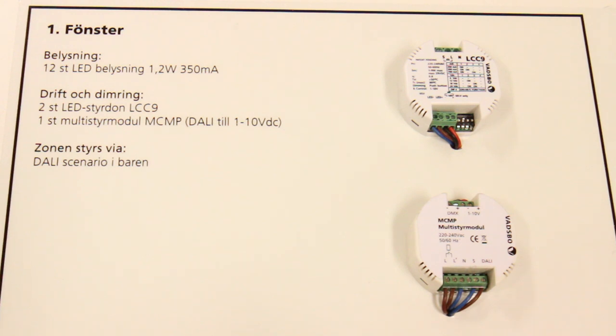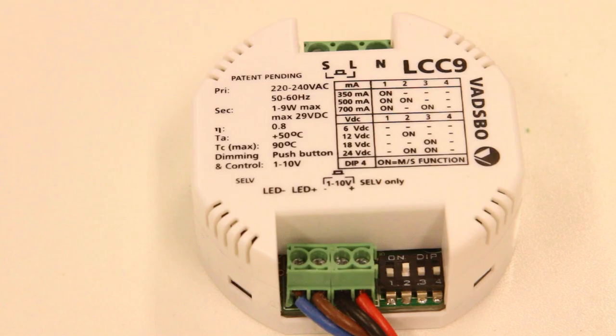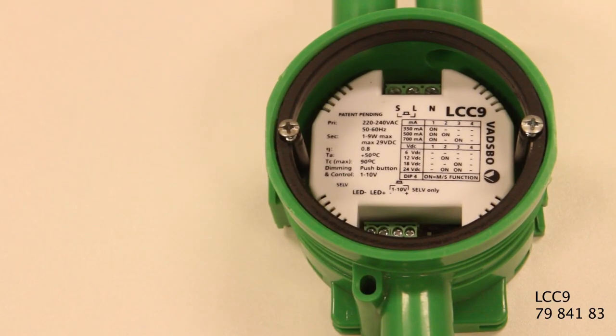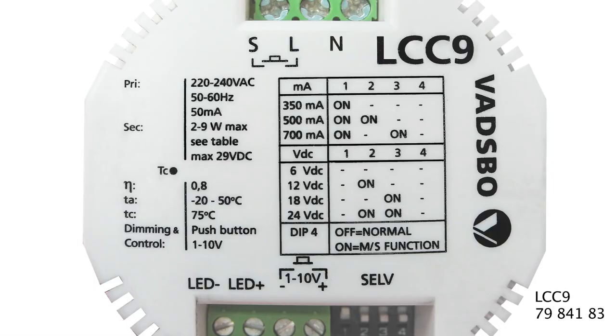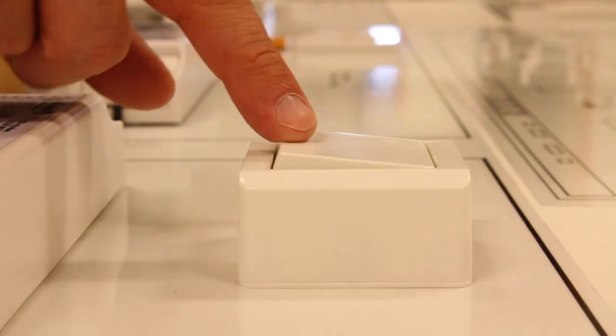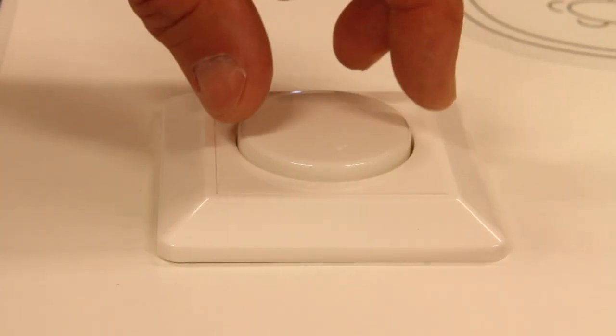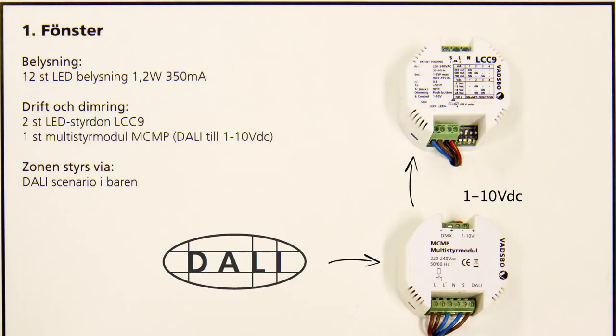LED control gear is a combination of a LED driver and LED dimmer in one device. LED control gear LCC9 can operate and dim LEDs up to 9 watts and can be placed in a wallbox. LCC9 can be set with DIP switches for constant current: 350, 500, and 700 milliamps, respectively constant voltage 12 and 24 volt. LCC9 is controlled by a momentary push button or a 1 to 10 volt control device and can be used in the DALI system with a converter from DALI to 1 to 10 volt, such as multi control module MCMP.